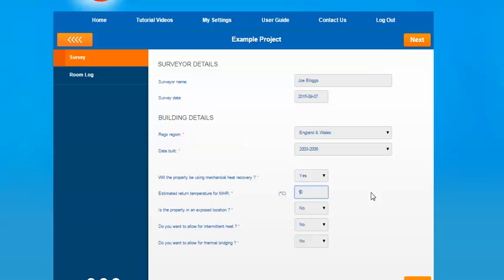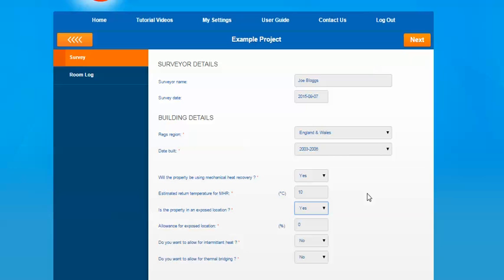The next question is if the property is in an exposed location — this means if the property is on top of a hill or close to the sea where it's open to the elements. If you select yes it gives you an option to allow a percentage for it. The domestic heat and design guide gives guidance to allow a 10% allowance, but we haven't set this as a default option so that you can make a judgment on the property you're working on. We'll put in the 10% based on the design guide for this example.